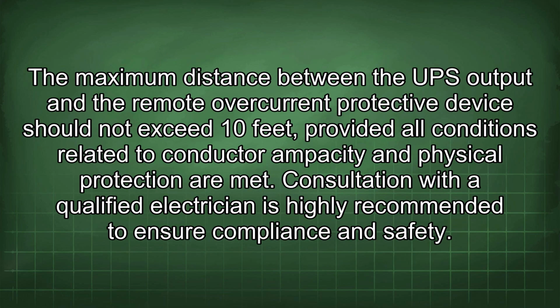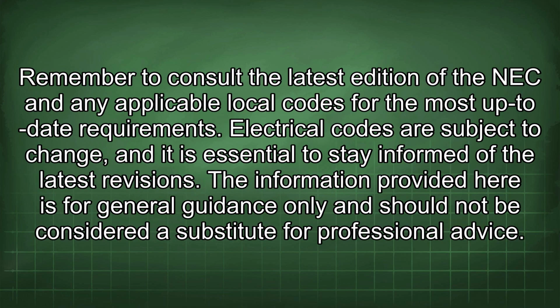The maximum distance between the UPS output and the remote overcurrent protective device should not exceed 10 feet, provided all conditions related to conductor ampacity and physical protection are met. Consultation with a qualified electrician is highly recommended to ensure compliance and safety. Remember to consult the latest edition of the NEC and any applicable local codes for the most up-to-date requirements.